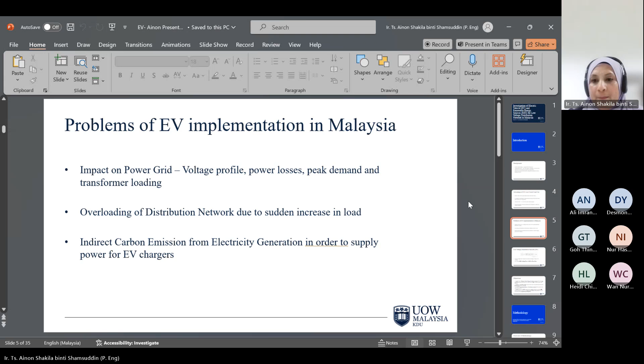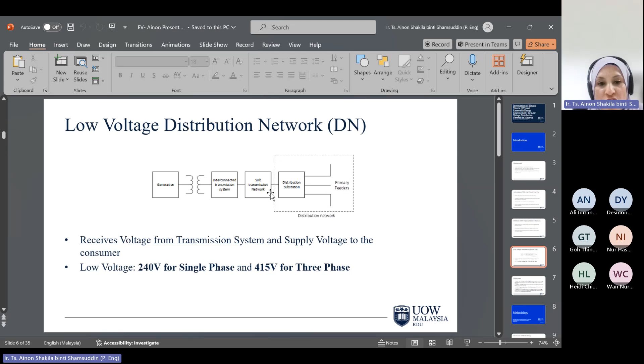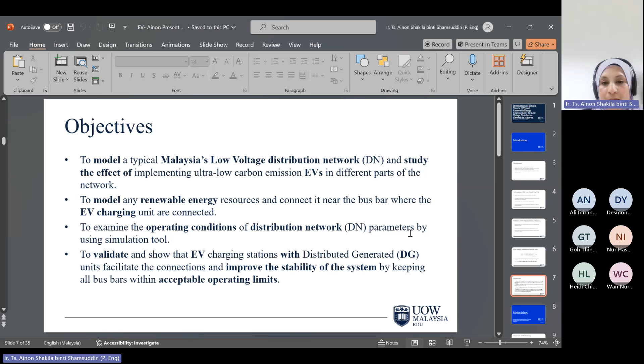This research will focus on modeling the distribution network to analyze the characteristics of the low voltage distribution and also examine the impact of integrating EVs into a low voltage distribution network. So the objective of this paper is to model a typical Malaysian low voltage distribution network with renewable energy and study the effect of implementing ultra low carbon emission EVs in different parts of the network by using PSCAD and also MATLAB Simulink. The model is validated to show that EV charging stations with distributed generation units facilitate the connection and improve the stability of the system by keeping all the bus bars within the acceptable operating limits.